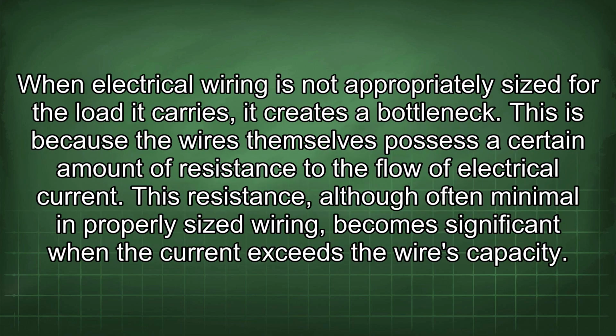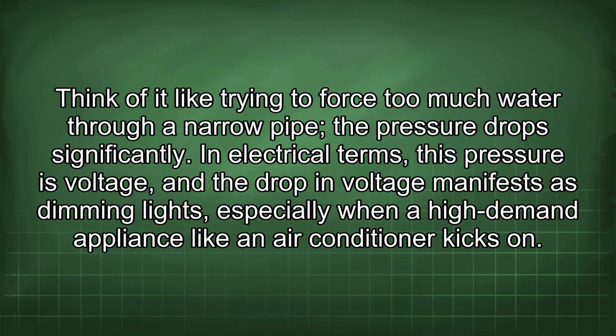When electrical wiring is not appropriately sized for the load it carries, it creates a bottleneck. This is because the wires themselves possess a certain amount of resistance to the flow of electrical current. This resistance, although often minimal in properly sized wiring, becomes significant when the current exceeds the wire's capacity. Think of it like trying to force too much water through a narrow pipe. The pressure drops significantly. In electrical terms, this pressure is voltage, and the drop in voltage manifests as dimming lights, especially when a high-demand appliance like an air conditioner kicks on.